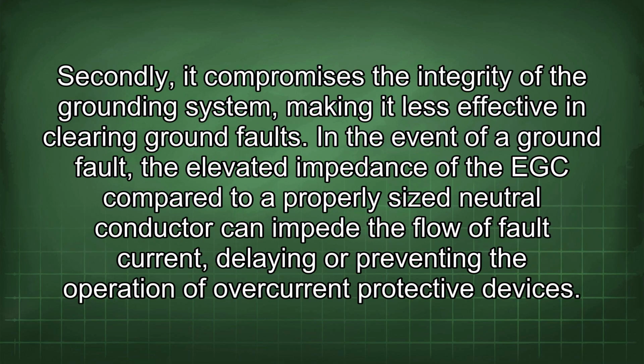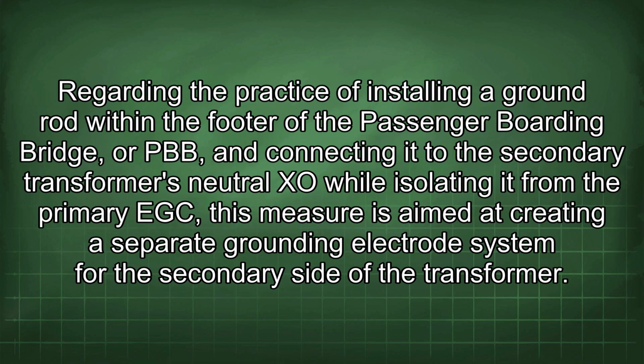Secondly, it compromises the integrity of the grounding system, making it less effective in clearing ground faults. In the event of a ground fault, the elevated impedance of the EGC compared to a properly sized neutral conductor can impede the flow of fault current, delaying or preventing the operation of overcurrent protective devices. Regarding the practice of installing a ground rod within the footer of the passenger boarding bridge, or PBB, and connecting it to the secondary transformer's neutral while isolating it from the primary EGC, this measure is aimed at creating a separate grounding electrode system for the secondary side of the transformer.